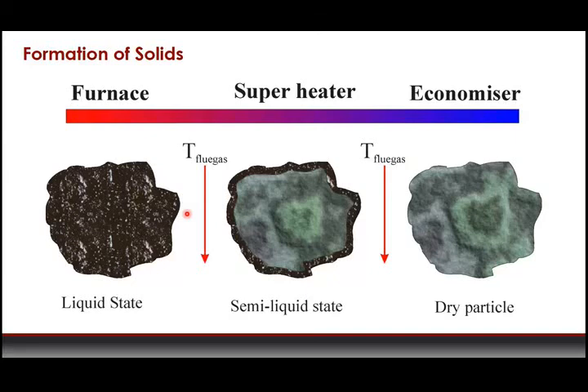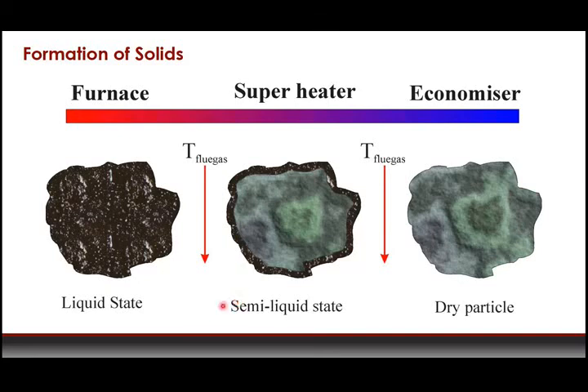In the furnace, you're more likely to have liquid or semi-liquid deposits forming on surfaces, because that's where temperatures are highest and combustion is occurring — so it's more likely that inorganic deposits are above their eutectic melting point and will be liquid or semi-liquid. Away from the furnace in the superheater area, temperatures are a little lower, so deposits there are more likely to be semi-liquid. The economizer has even lower temperatures, which is why deposits formed in that area tend to be characterized as dry particulate forms.